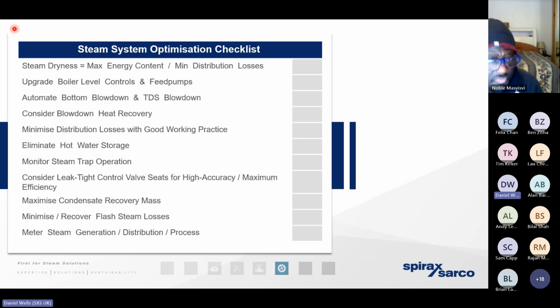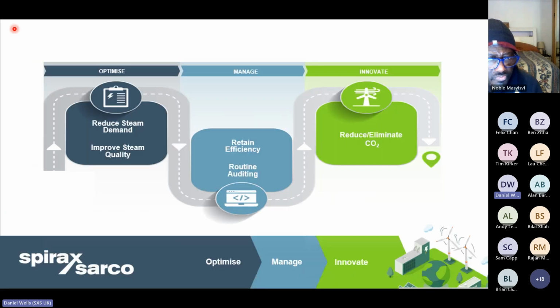As I said, it's the wrong thing to do to look at those innovations straight away. If our existing steam boiler is producing 10,000 kilograms of steam per hour, if we can optimize the system so that the boiler now only needs to produce 7,000 kilograms of steam per hour, that's a very, very quick win. That's a huge step forward in demonstrating that we've started to decarbonize our steam system. And it's things that we can do here and now today.